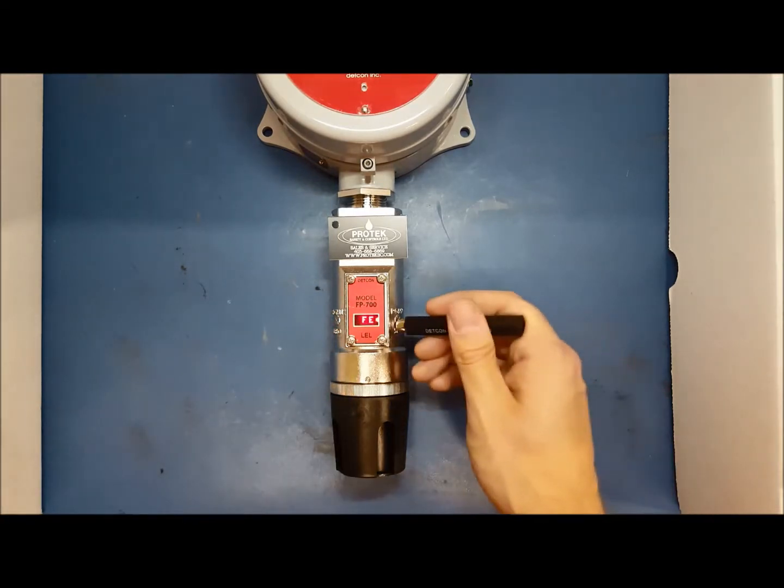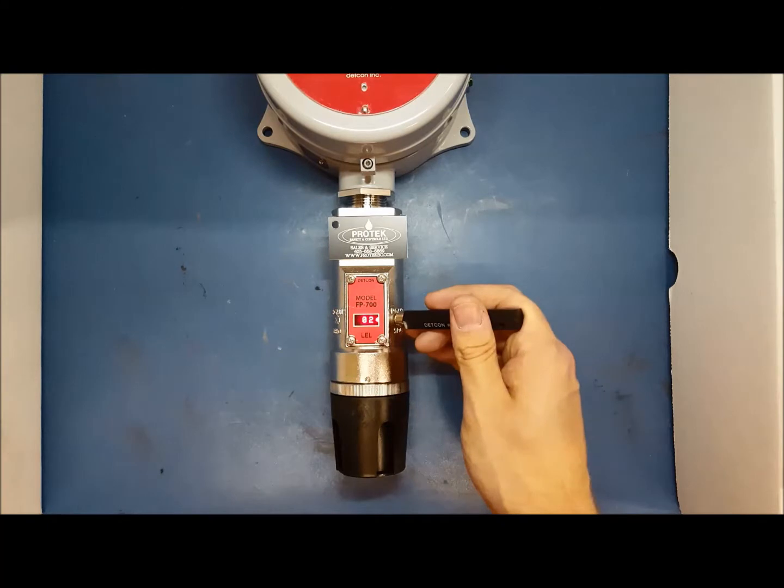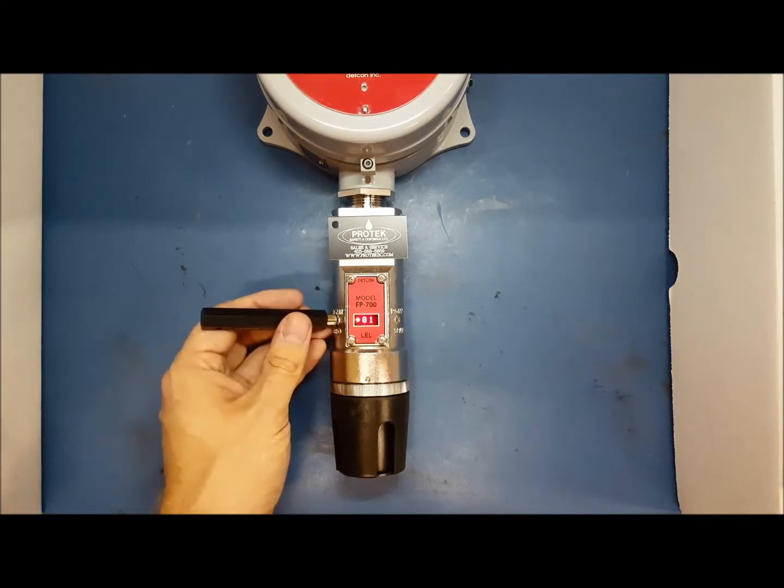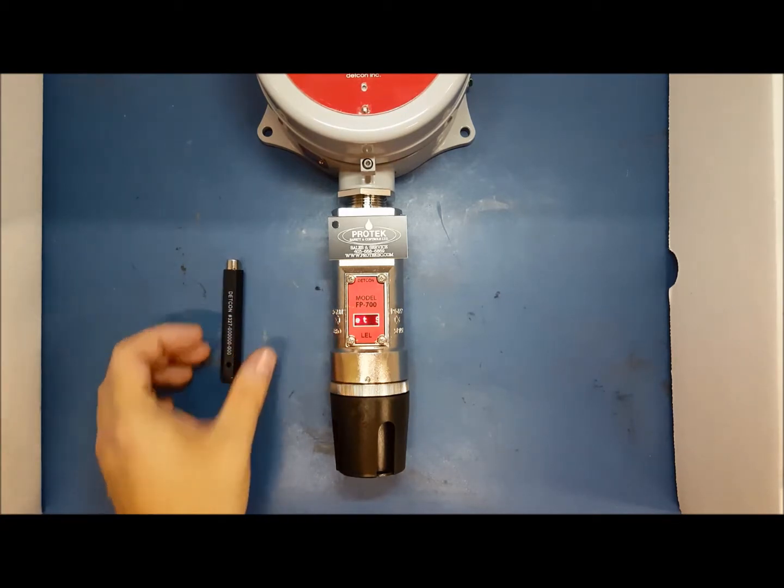Using your magnet, flick over PGM2 to increase the number and flick over PGM1 to decrease the number. Once you have the ID number that you need, hold the magnet over PGM1 until the display reads ID Saved.